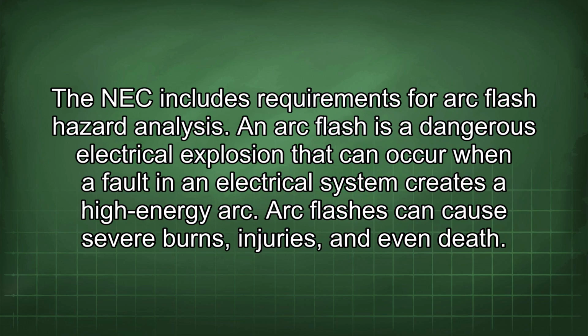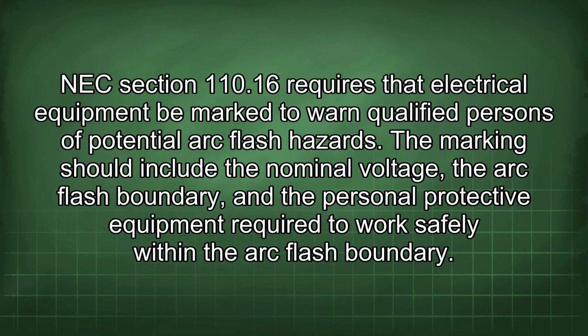The NEC includes requirements for arc flash hazard analysis. An arc flash is a dangerous electrical explosion that can occur when a fault in an electrical system creates a high-energy arc. Arc flashes can cause severe burns, injuries, and even death. NEC Section 110.16 requires that electrical equipment be marked to warn qualified persons of potential arc flash hazards. The marking should include the nominal voltage, the arc flash boundary, and the personal protective equipment required to work safely within the arc flash boundary.